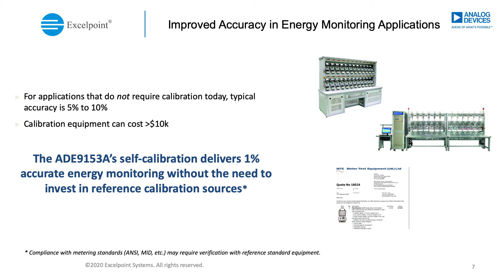In the market now, for meters using the shunt measurement method, they could face some issues over time of use. One of the main issues is shunt overheating. Why does shunt overheating occur? There are mainly three reasons: environmental conditions, high current, and poor in-case airflow. Shunt overheating may result in unwanted error in the shunt value, which will affect the accuracy of your metering system.